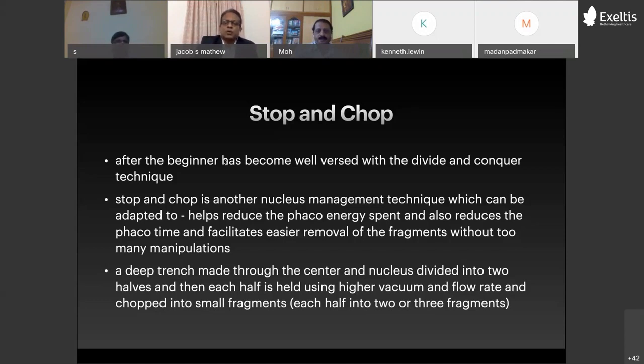You know how the vacuum at the hold works, how the power has to be changed. When you're doing your trench, you have to have a higher power with less vacuum and flow rate. But when you're doing the fragment removal, you have to increase your vacuum setting as well as the flow rate, and the hold should be very good. So the fragments should come to the tip, as well as the power should be adequate to remove the kind of hardness that the nucleus is having. So all these things one learns, and then one feels that the surgery can be done a little more faster probably, and that is the stage when you look forward to the technique called stop and chop.